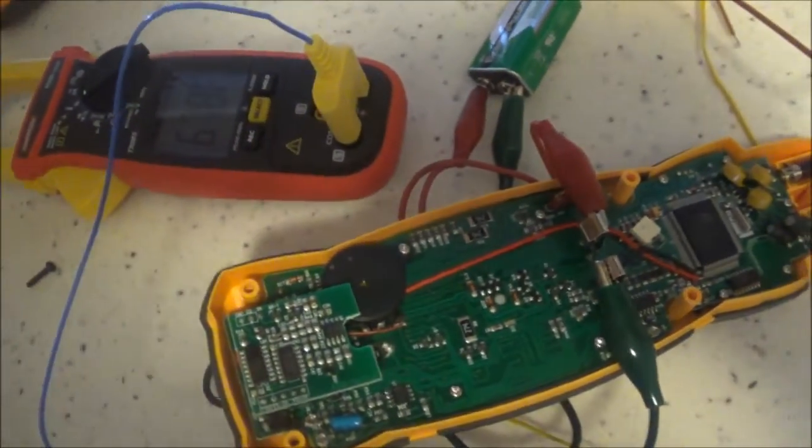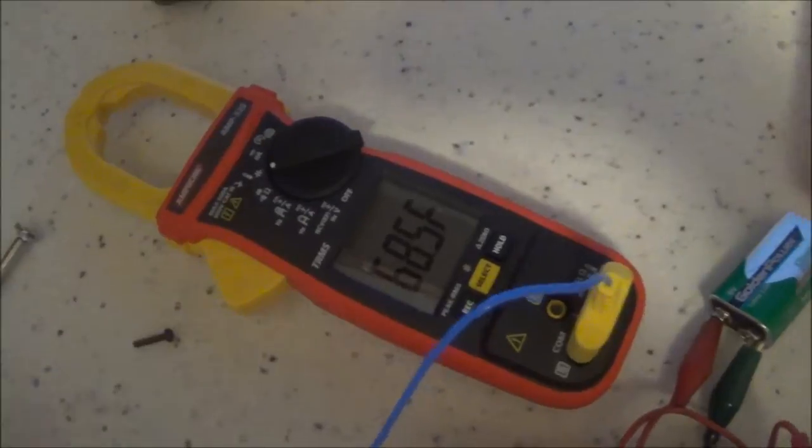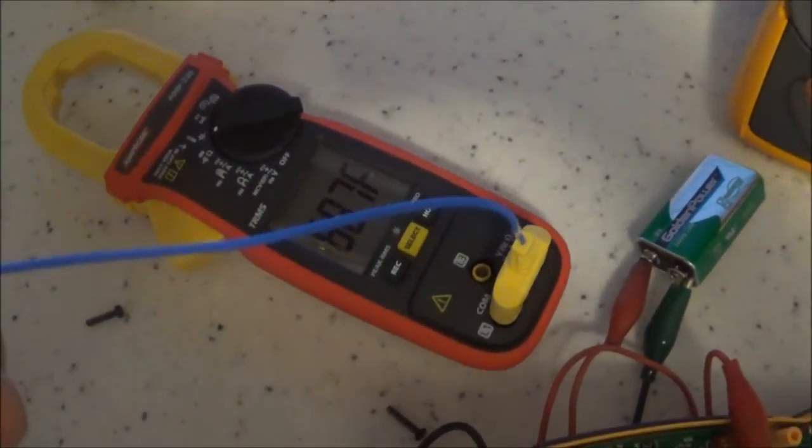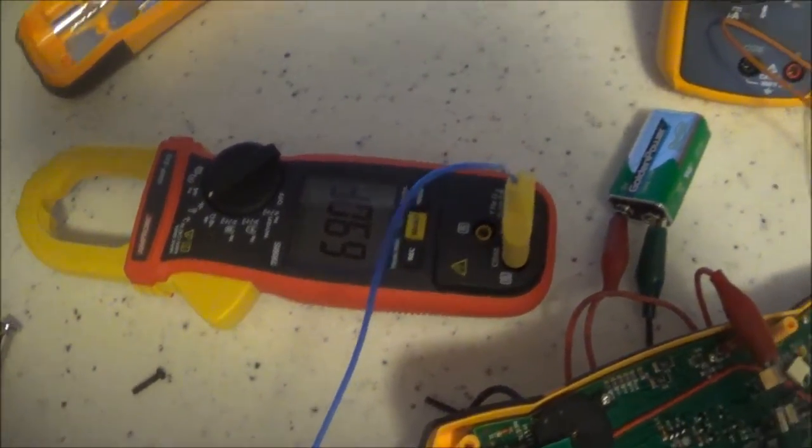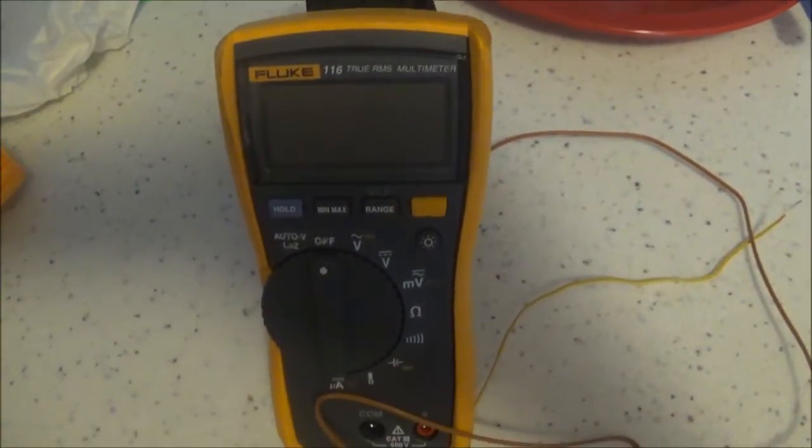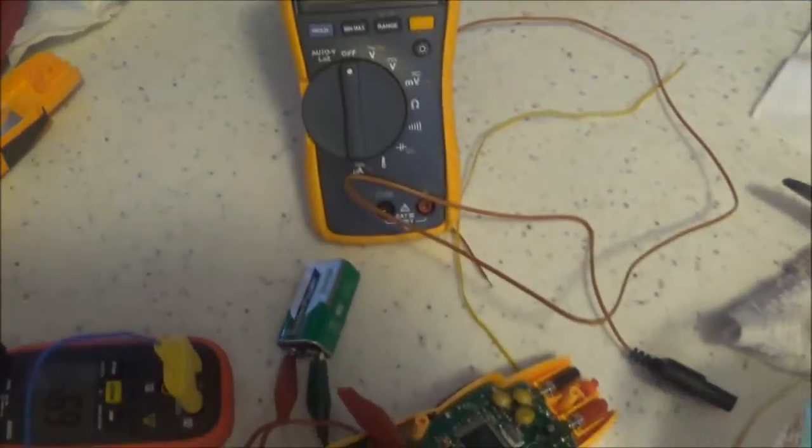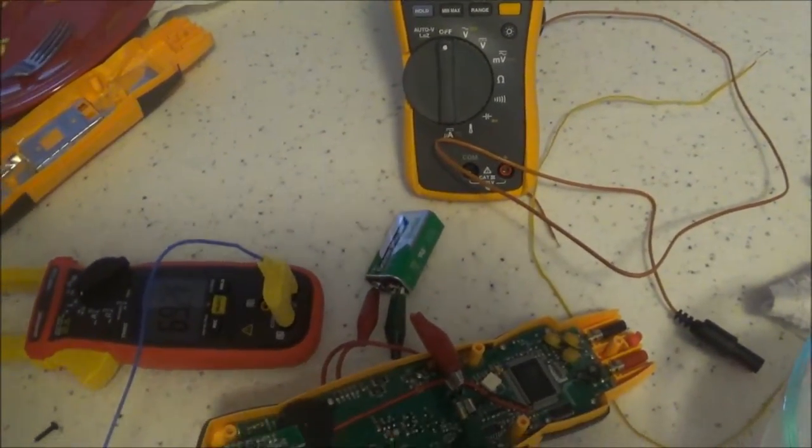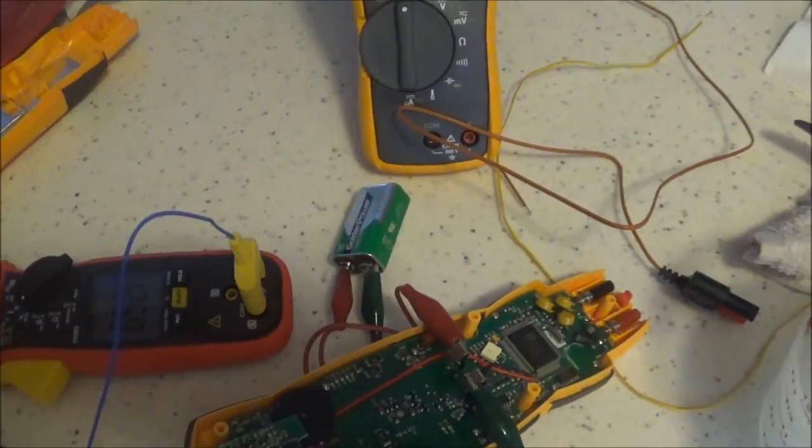HS36, not bad for temperature, it does well too if you use its leads. AMP 320 meter itself, temperature is non-adjustable, but if you use the factory lead, 32 degrees, it seems to be set if you use the ice bath calibration method. The Fluke runs a little low, half a degree on the 32 degree setting, and I'm not going to reset it. So there's a little overview of calibrating your temperature settings on a different line of multi-meters and temperature meters. Thanks for watching.